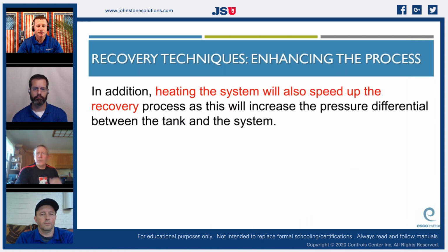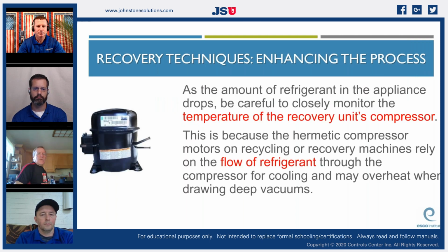And the other side of that is you can warm the system up. I think Brian mentioned yesterday turning on crankcase heaters or defrost controls. Yeah, you warm the refrigerant up and it increases the pressure and it's ready to leave. Decrease the pressure of the recovery cylinder and it's ready to accept. So it's kind of just simple science. Recovery units' compressors do use the flow of refrigerant to keep them cool, just like our air conditioners do. Almost all residential air conditioners use the refrigerant to keep the compressor cool.